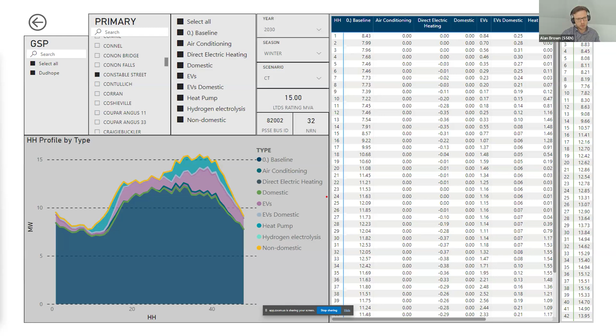I mentioned the constraint analysis. We talked about potential need to invest in one substation, but this gives a bit more flavour, with my system planning hat on, about how we used to do these studies. You'd have your future demand curves for each substation. This example is a ring network on our Keith 33 kV network in the northeast of Scotland, so it's a ring circuit.